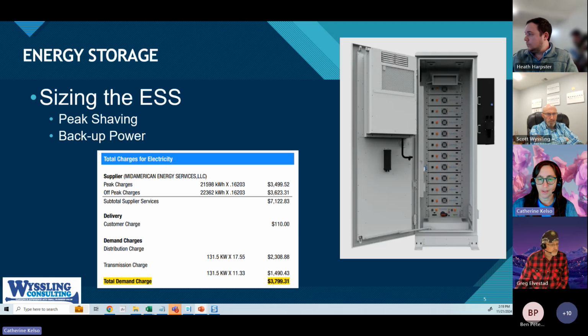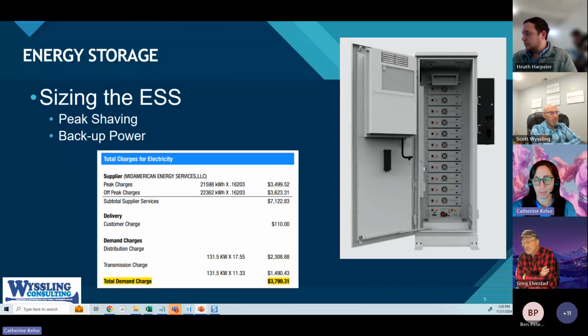Just to back up a minute to explain what the demand charge is: at some point, this facility drew 131.5 kilowatts from the grid at one time for 15 minutes. And they could get charged for that amount for the next 3 months because they hit that demand. Some electric companies even have a worse penalty: if you hit a certain demand, you end up in a whole different rate code and all of your power bill is higher. So it's a big deal to be able to deal with this.